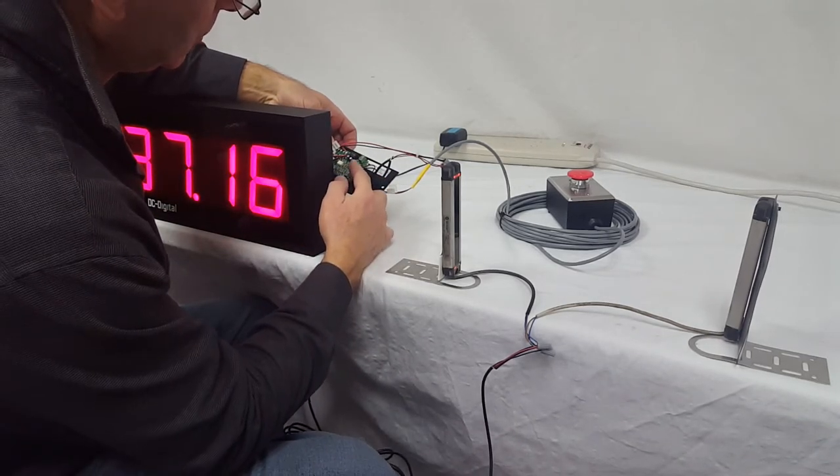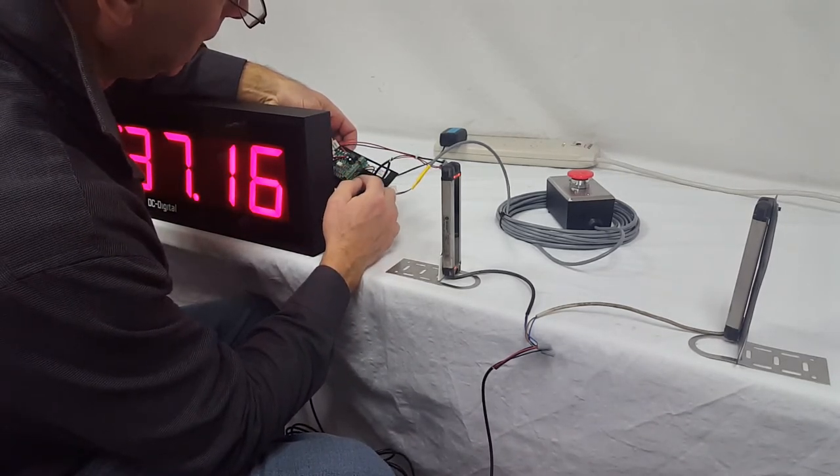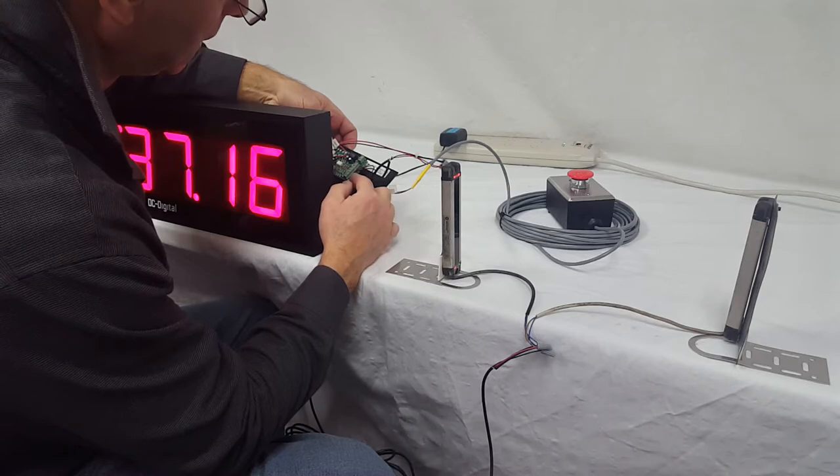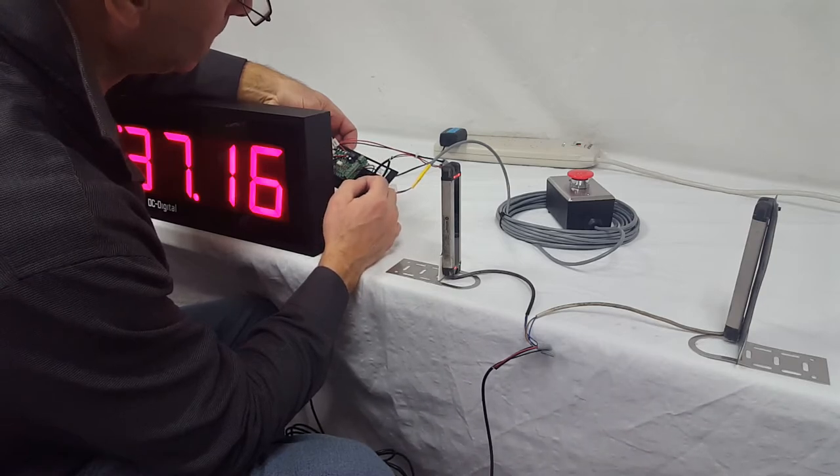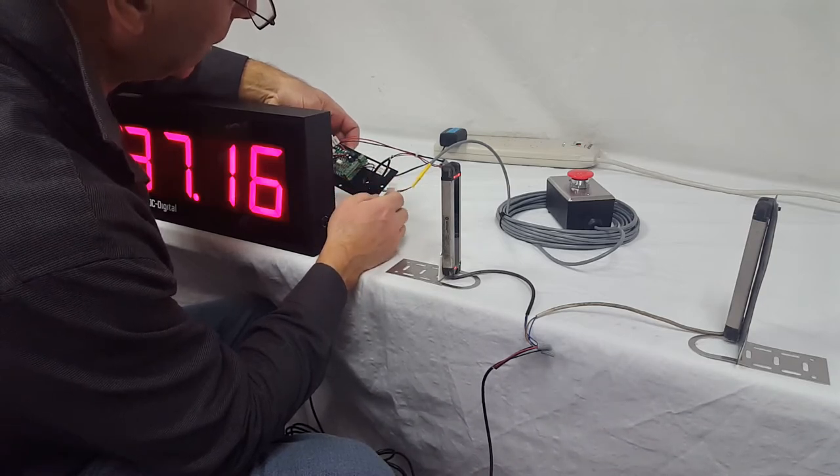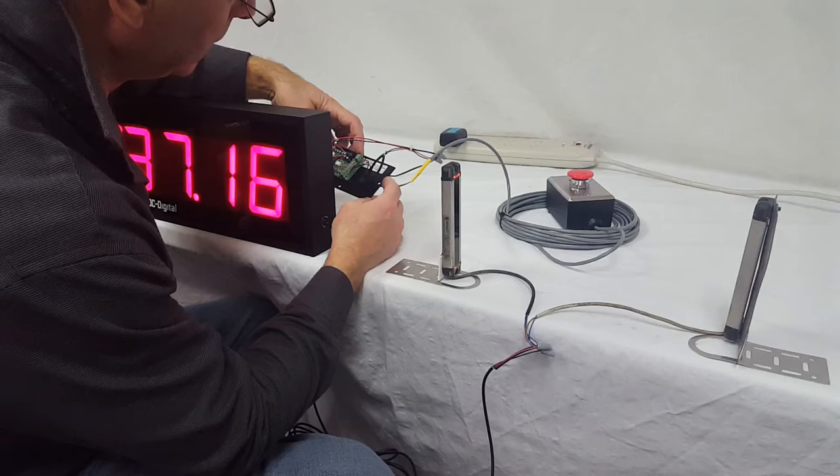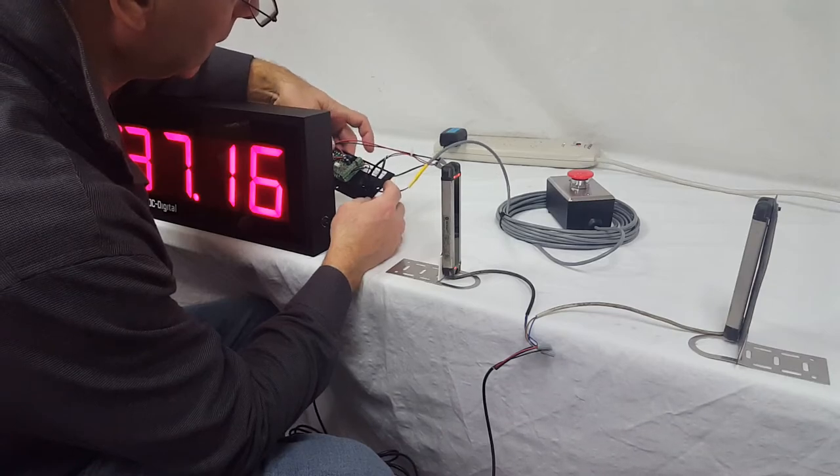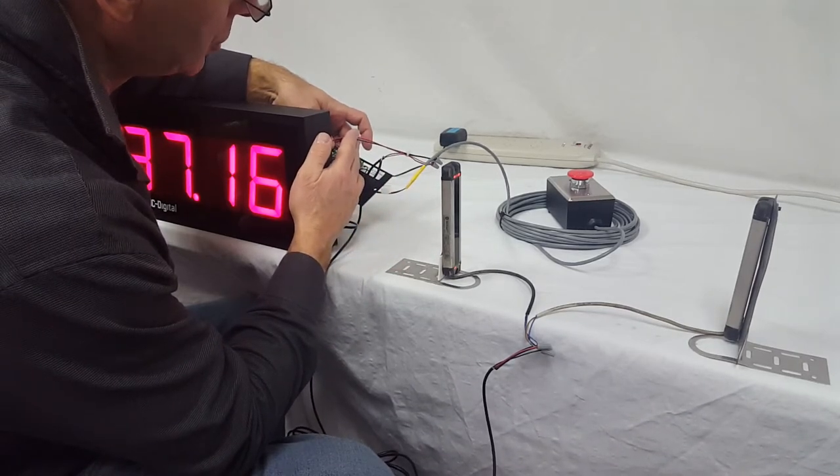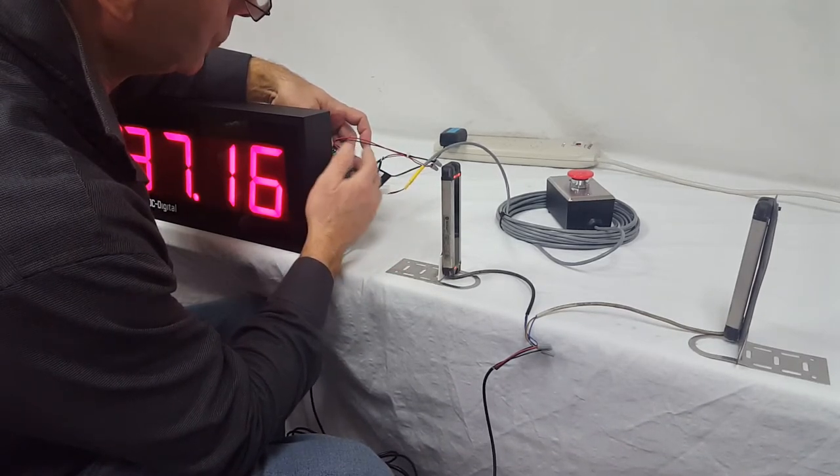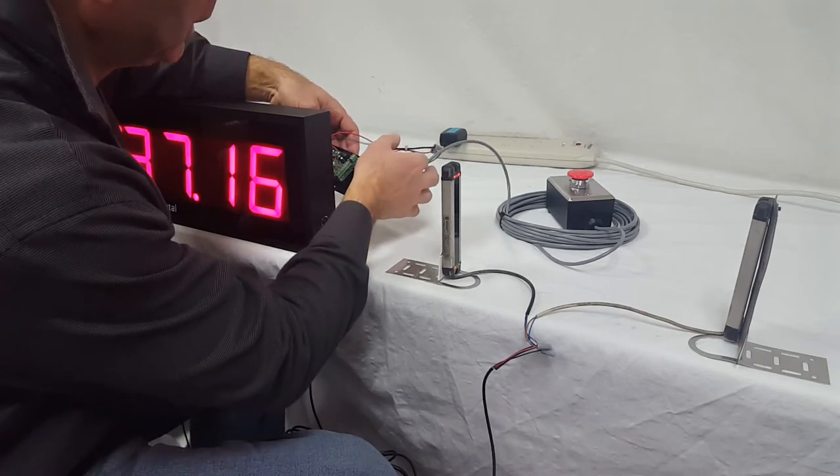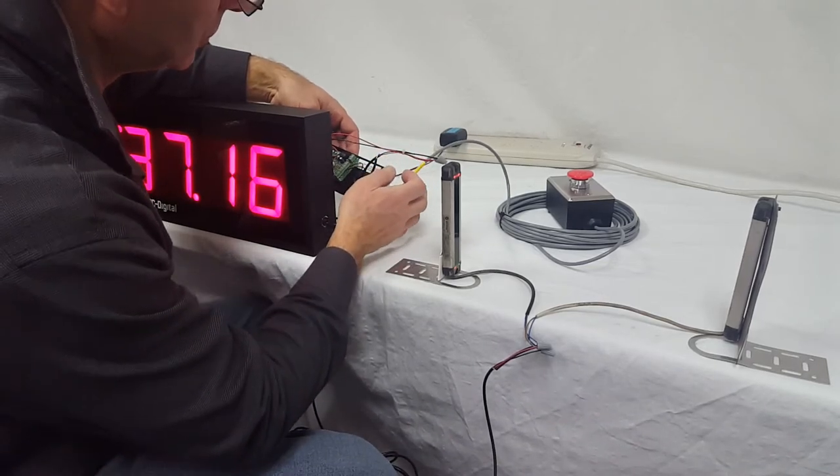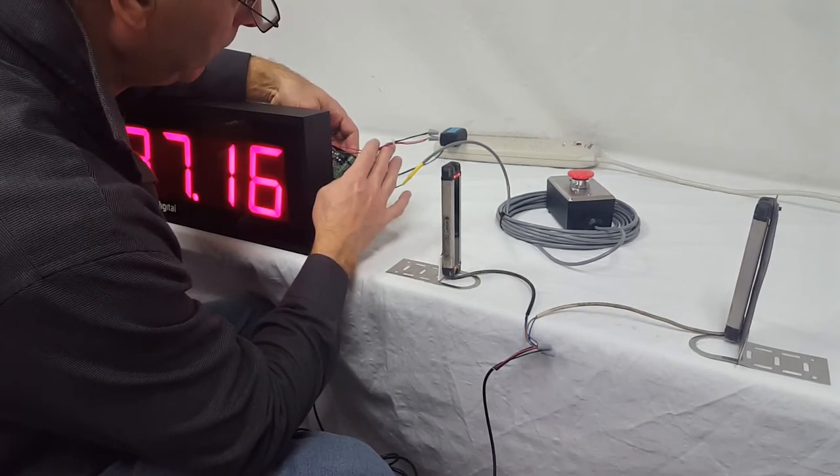There's three terminals for your connections, your PNP connections or your contact closure. We also have another connection for 24 volt input if you like. We provided sensor power since we knew they were connecting to a sensor and they wanted that all in one package.